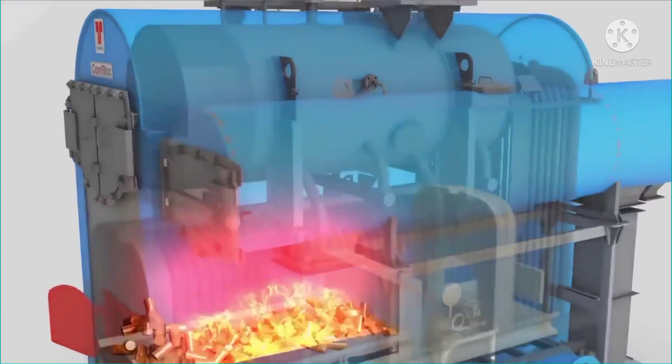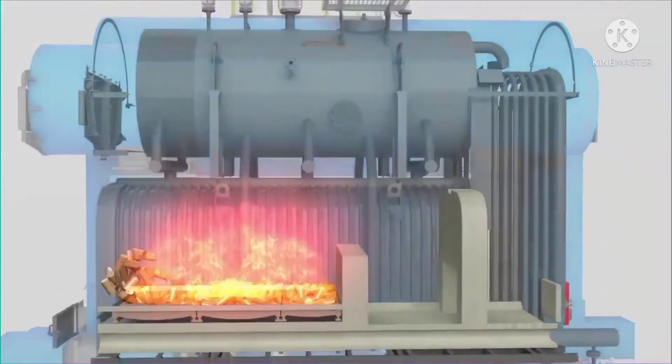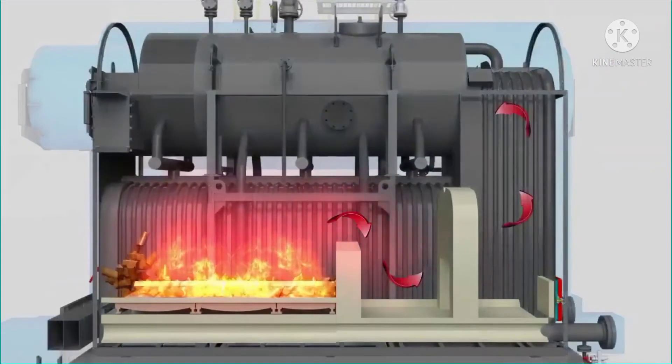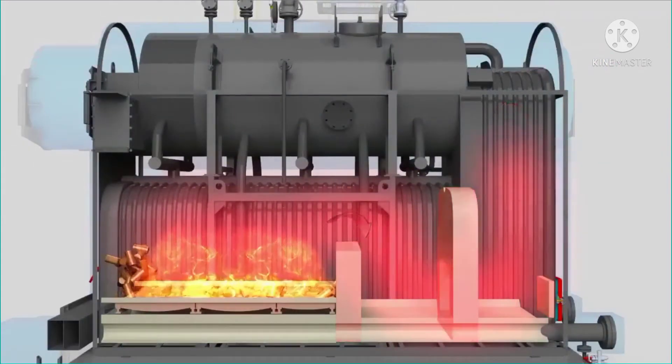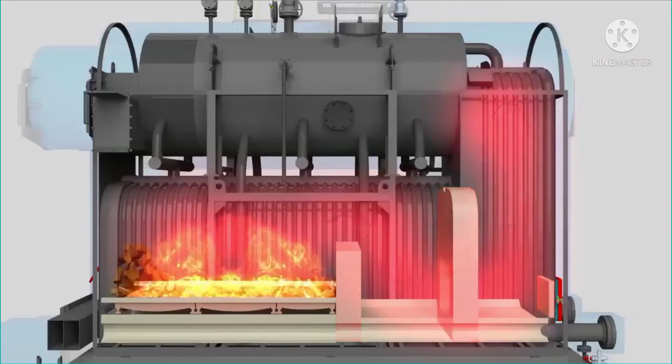Meanwhile, the flue gases from the combustion chamber travel to the reversal chamber through the refractory baffle walls. These walls help increase the length of passage of the flue gas, thus increasing the residence time of combustion and also help in better emission.